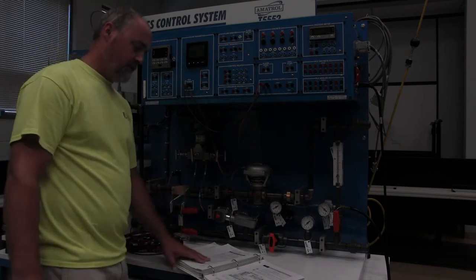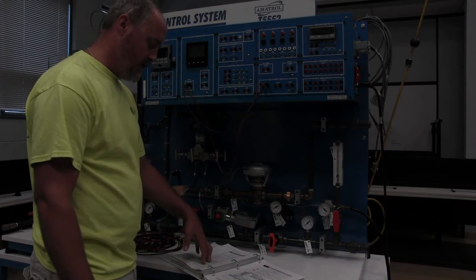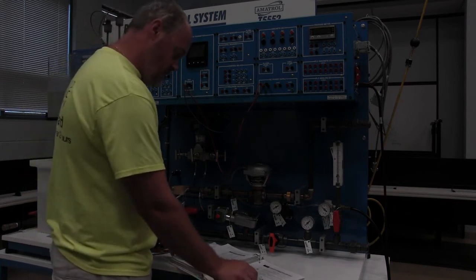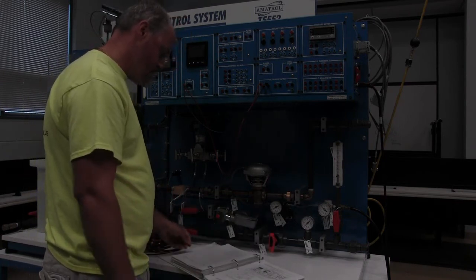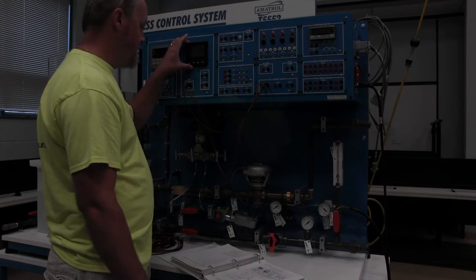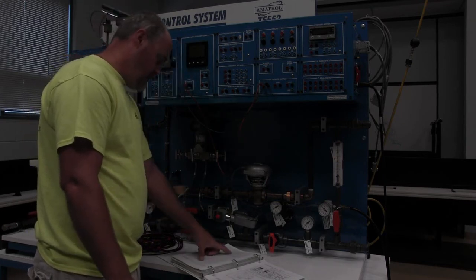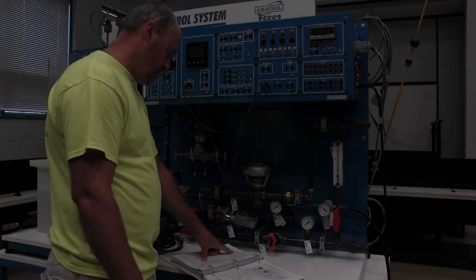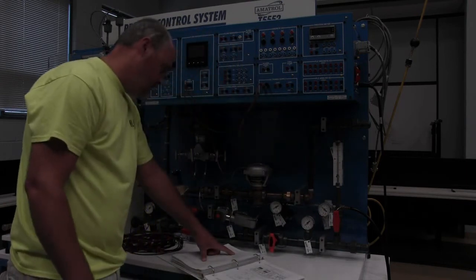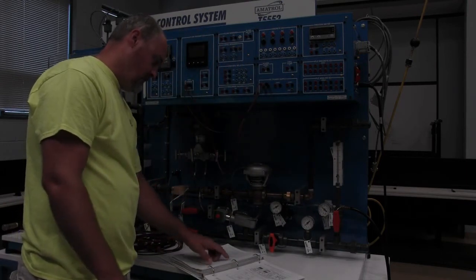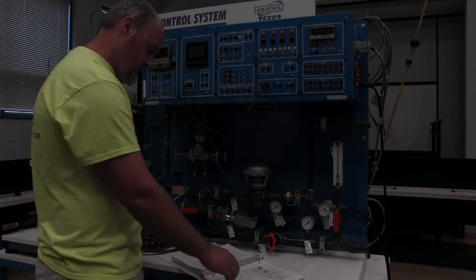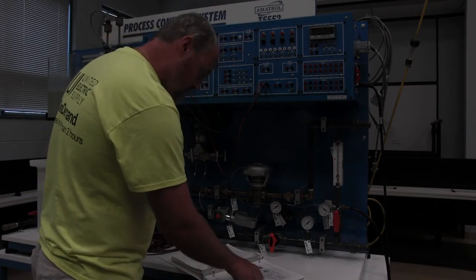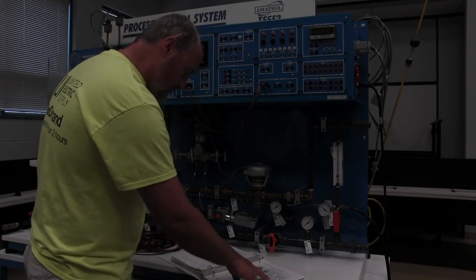All right, so we're going to operate a flow control loop using a paddle wheel sensor. This is a Signet GF transmitter, and here's the paddle wheel. We're to connect the circuit as shown. Set the pressure regulator to 20 psi, which it is. Fill the reservoir, open the valves. Connect the circuit as shown. So we are going to take, and we're going to run power.